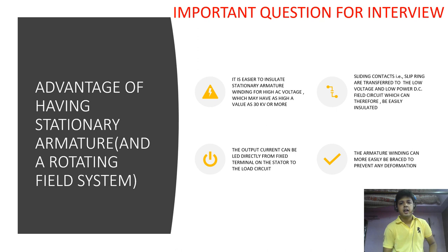So it is easier to insulate the stationary armature winding for AC voltage which may have as high as value like 30 kV or more. Second, in the sliding contact, if we put the armature on the rotor then we have to use sliding contact like slip ring from high voltage side. But if we put the rotor field contact then we have to give only 120 volt, 125 volt. So slip rings are transferred to the low voltage side and the low power DC field winding which can be therefore easily insulated.